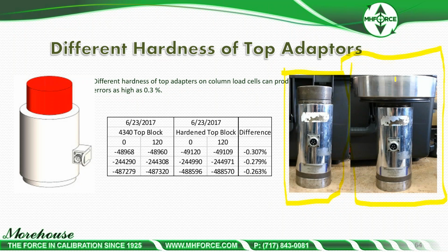I said, well, let's just test. The customer sends it in. We use our adapter here versus what the customer uses. And I know several labs are not using the top and bottom blocks. They're using their own adapters, which is so wrong on so many levels. But when people don't send top blocks in, this is the problem they get into. They just send a load cell and say calibrated, and we say, do you have top blocks? And they say, do it with yours. That's the problem. I'd rather never do that. I'd rather always do this situation where we have a top block and they know it.